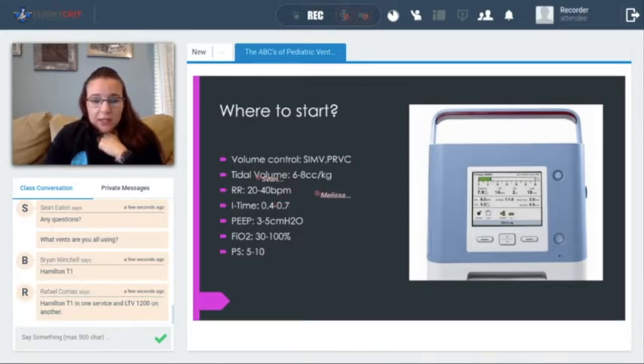Depending on what mode you're in, be careful, and every ventilator is different. I'll tell you, with our ventilator, our issue is that if we pick infant mode, it locks us into a 0.3 I time. That is a very aggressive I time for a pediatric patient. A 0.3 and 0.4 is something that you deal with in the NICU population. So if you have a 1 or 2 month old baby, locking them into a 0.3 I time is a problem.